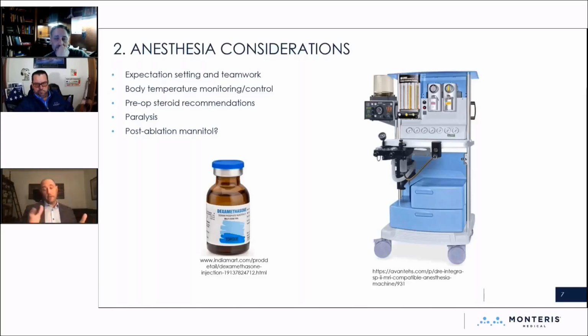When you think about it, I don't know how much you guys know about the physics of this, but the phase change data from the MRI is not actually calculating a temperature. It's calculating a delta temperature from the reference points that you set as you go around, and the software picks these points around the periphery of your field. So those reference points, you really need them to be accurate, because if you're not accurate, then when delta is calculated and takes you to your lesioning temperature, your lesioning temperature is not going to be accurate. And so you're either going to be under or over, which means you could either be causing damage to surrounding structures that you don't want to, or you could be under treating your lesion. So having an accurate body temperature and probe temperature to begin the case are really important.